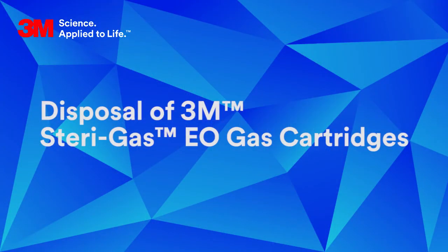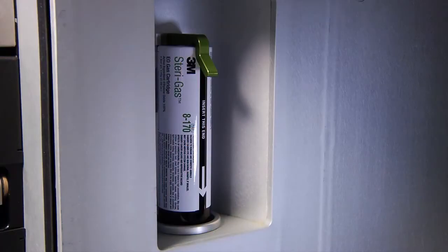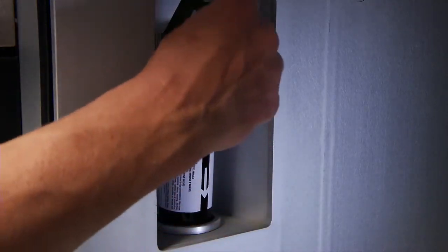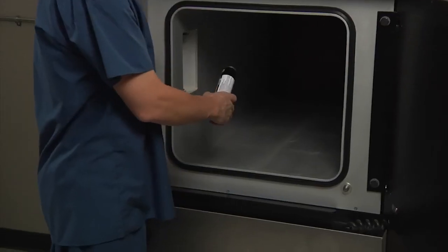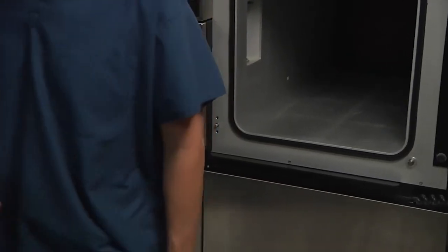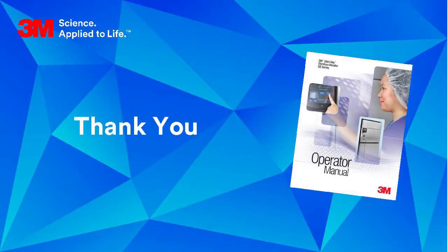The empty 3M Sterigas EO gas cartridge should be aerated for a minimum of 2 hours before disposing of the cartridge. This can be completed as part of the normal aeration cycle. After aeration is complete, remove the cartridge from the cartridge holder and dispose of the cartridge in a non-incinerated waste receptacle or recycle the cartridge per your facility's recycling procedures. This concludes the 3M Sterivac Sterilizer Aerator GS Series in-service training. Please refer to the 3M Sterivac GS Series Operator Manual for complete details.